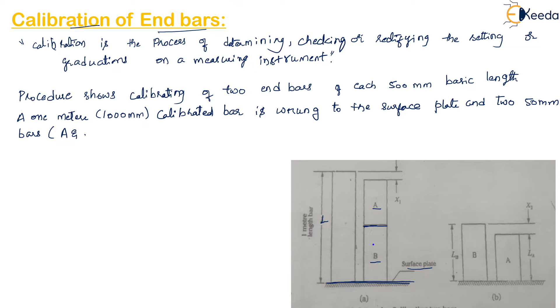So a 1 meter bar, that is a 1000 mm calibrated bar, is rung to the surface plate, and the 500 mm bars, A and B, are rung together to a basic length of 1 meter, which is then rung to the surface plate, as shown in this figure.